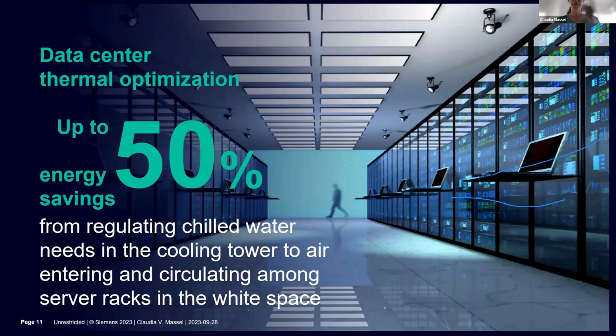The other topic that gets us to this 50% energy savings is white space optimization. That means looking at where in the data center more cool air needs to be directed—looking at the fans. Maybe you don't need all the fans turned on at the same time. Maybe part of your data center isn't even used because of too-old equipment that's been deactivated, so you don't need to send air there. You just need sensors throughout your data center, and the data from those sensors can be used in real time to control the fans directing the air. This also greatly reduces the risk of server failure, because you ensure they stay at the temperature they should be staying at.